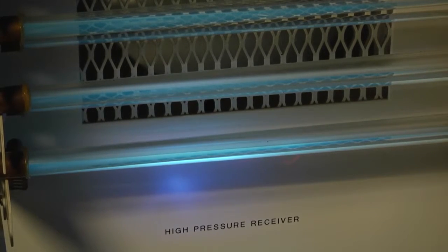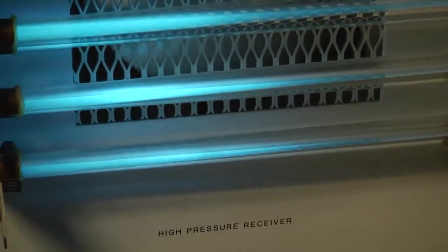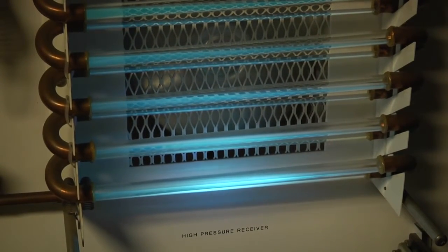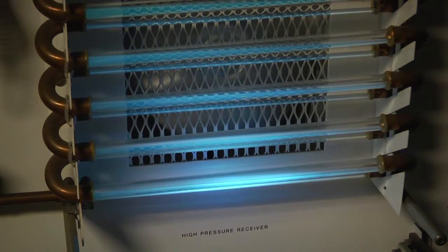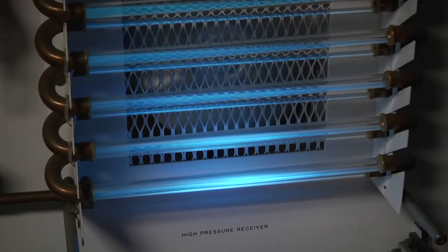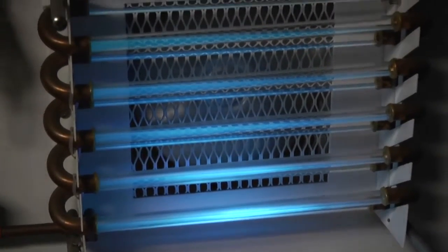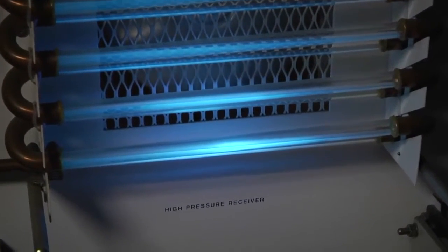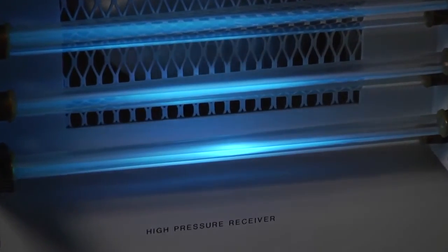Now, the metering device will quickly drop the pressure and the saturation temperature, feed refrigerant back to the evaporator, and the process will continue over and over again. We cycle the same refrigerant throughout the system all day long. The refrigerant doesn't get old, it doesn't get tired, it doesn't wear out, or lose its thermodynamic properties. It just continually changes state, from a liquid to a vapor in the evaporator, then from a vapor to a higher temperature vapor in the compressor, and then from a vapor to a liquid in the condensing coil. And it repeats the process over and over again.